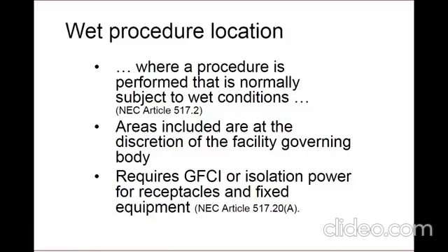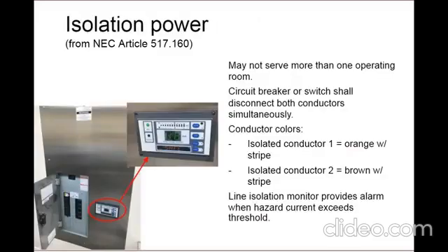NEC 517.20A requires additional special protection from electric shock in wet procedure patient care spaces. The first option is to install a power distribution system that limits the ground fault currents without interrupting the supply. An isolated power system will provide this type of protection. The second option is a system that interrupts the supply if the ground fault current exceeds 6 milliamps. This could be GFCI protection. In an operating room where invasive procedures occur, interruption of the power supply could have devastating consequences. Normally, an isolated power system is installed in these spaces.